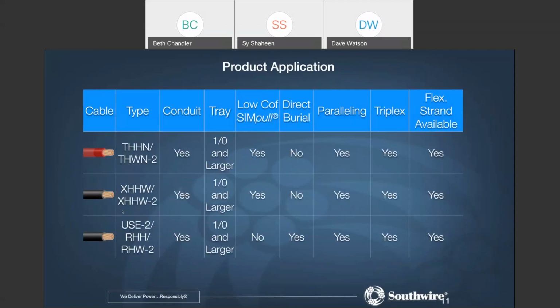So in terms of applications in comparing these products, you'll see a lot of similarities. I want to point out in the center, you'll see the low COF, which is low coefficient of friction, SimPull. The THHN and XHHW style conductors are manufactured with this SimPull technology. This makes them much easier to install in conduits, and you do not need to use a cable lube when installing these products. The USE RHH RHW product, however, is not a SimPull product. So if you're going to be pulling that product through conduit, you will need to use a lubrication product for that.